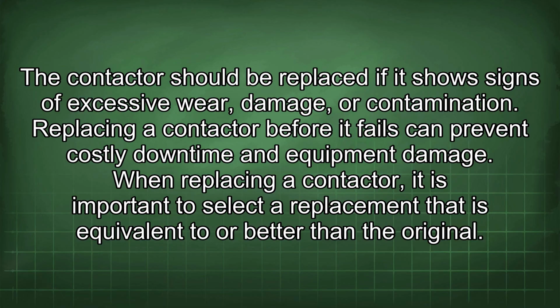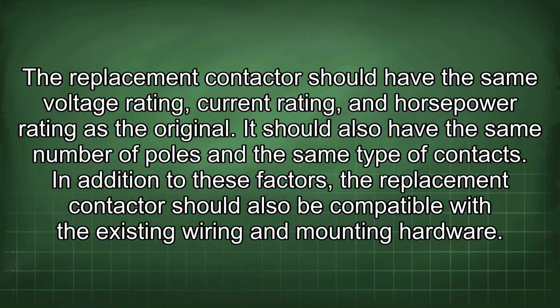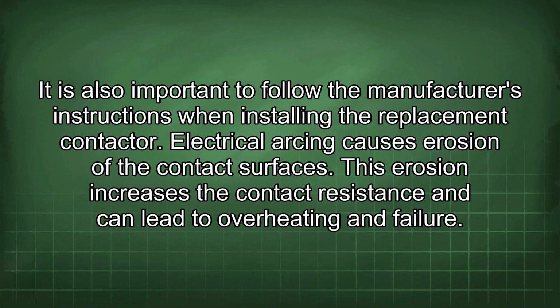When replacing a contactor, it is important to select a replacement that is equivalent to or better than the original. The replacement contactor should have the same voltage rating, current rating, and horsepower rating as the original. It should also have the same number of poles and the same type of contacts. In addition to these factors, the replacement contactor should also be compatible with the existing wiring and mounting hardware. It is also important to follow the manufacturer's instructions when installing the replacement contactor.